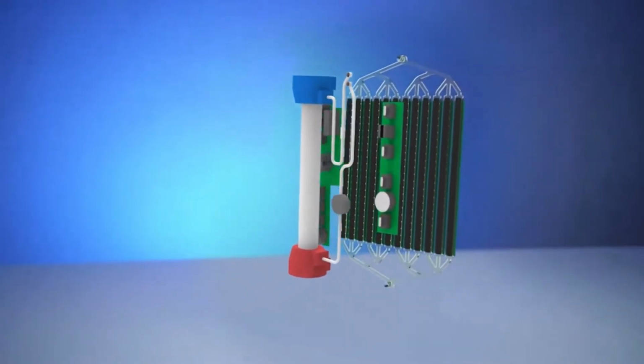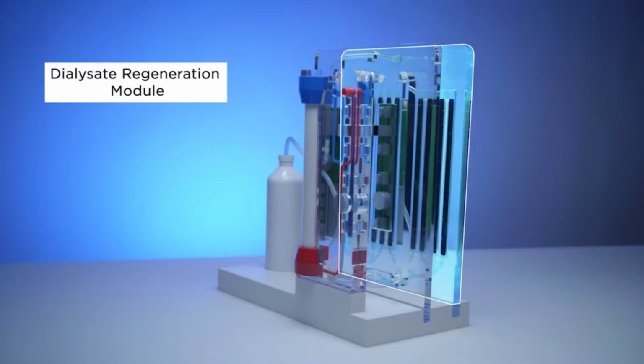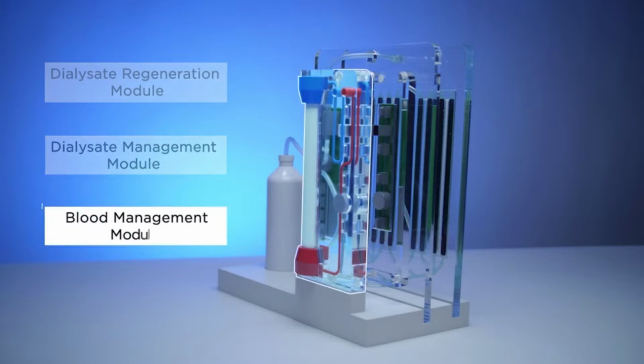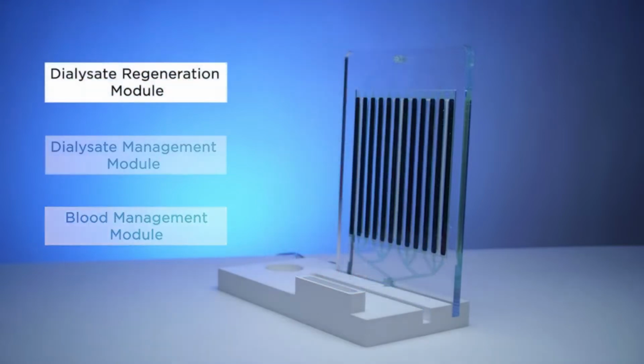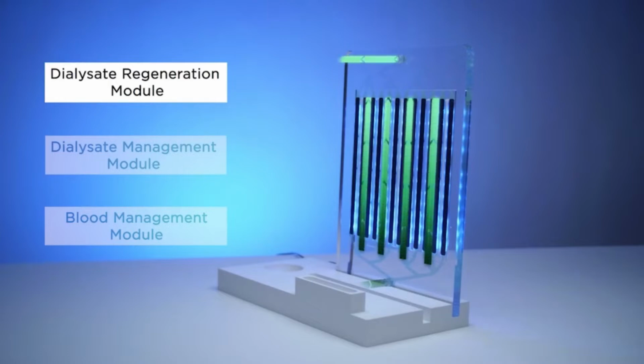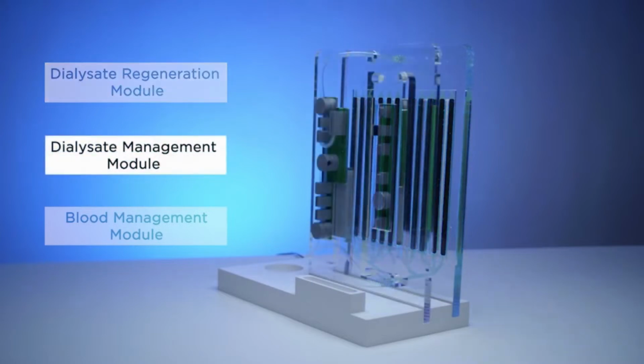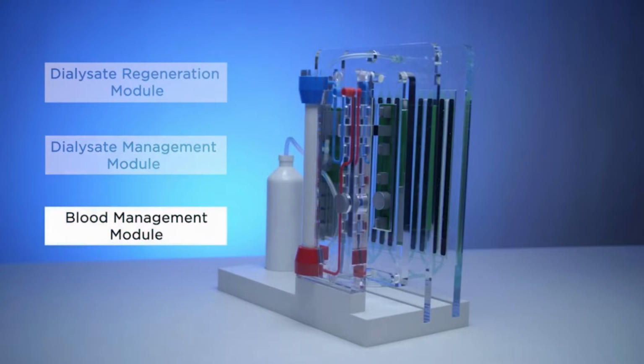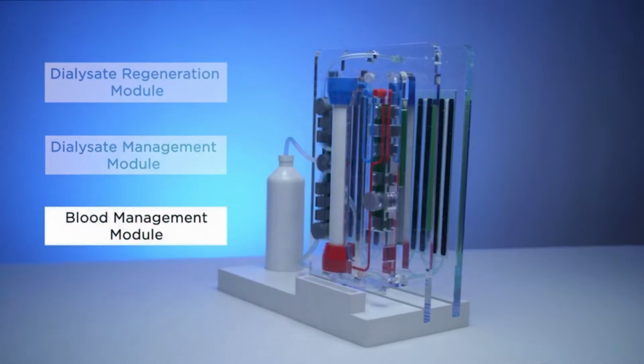The Active is comprised of 3 modules: the dialysate regeneration module, the dialysate management module, and the disposable blood management module. The dialysate regeneration module removes toxins from the spent dialysate. The dialysate management module directs the dialysate through the Active and contains the electronics, software, pumps, and sensors required to safely and effectively manage the dialysate and overall device operations. This module also proportions electrolytes into the regenerated dialysate stream returning to the dialyzer. The blood management module is a disposable, easily replaceable cartridge that integrates the dialyzer, flow channels, sensor interfaces, and bloodlines.